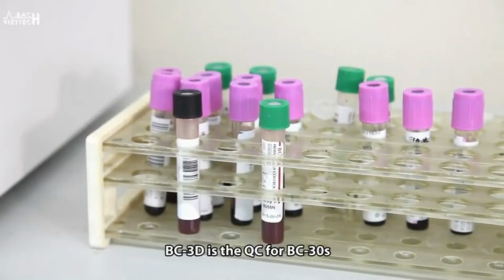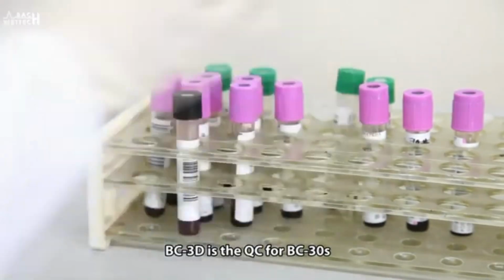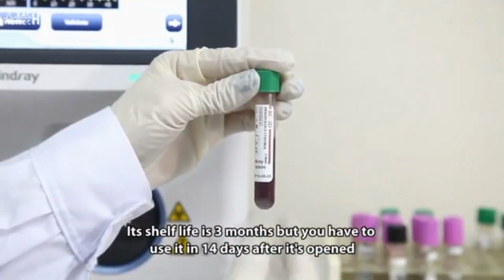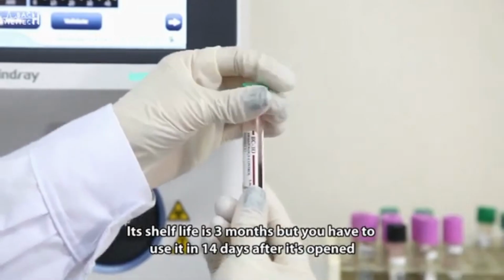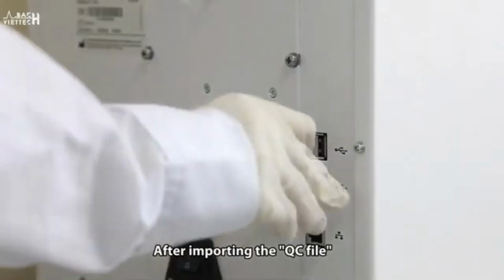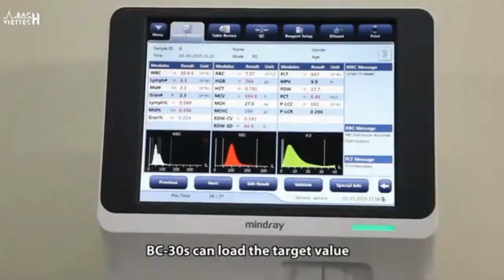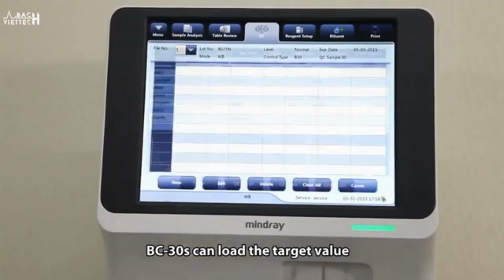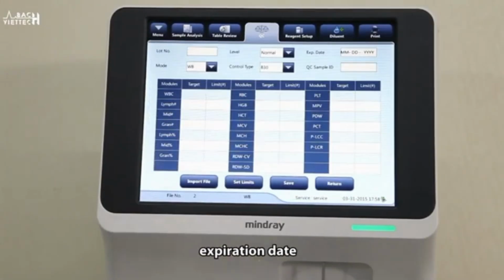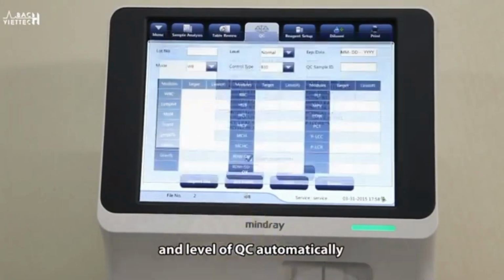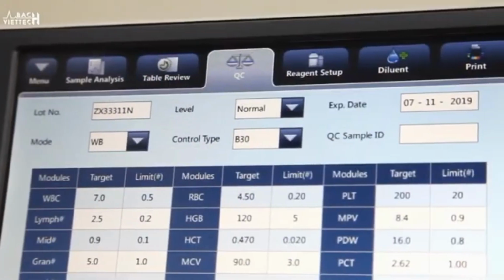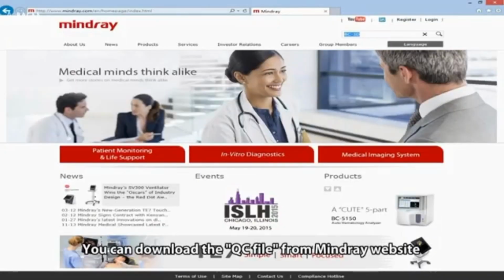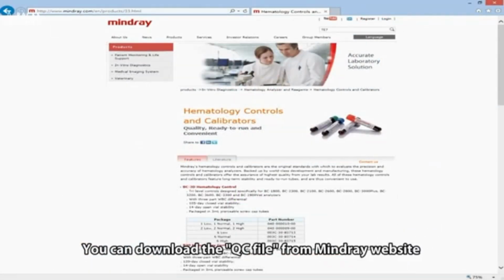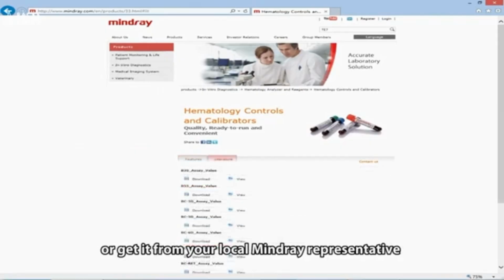BC3D is the QC for BC30S. Its shelf life is 3 months, but you have to use it in 14 days after it's opened. After importing the QC file, BC30S can load the target value, lot number, expiration date, and level of QC automatically. You can download the QC file from Mindray website or get it from your local Mindray representative.